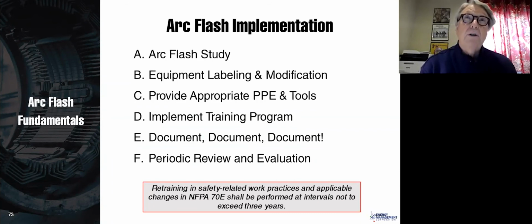And arc flash stickers are grandfathered. So it doesn't matter when they were put on, as long as they were legal and accurate at the time that they were installed, you'd never have to change them. Now, I'm saying that in 2021, they could come out and say, okay, now we're not going to let you grandfather anymore or something, but I don't think they're going to do that. I really think that this is going to be the case. They've pretty much made a precedent of that. Arc flash stickers never expire, and the only reason you need to replace them or reevaluate them is if you made a significant change to your power distribution system.